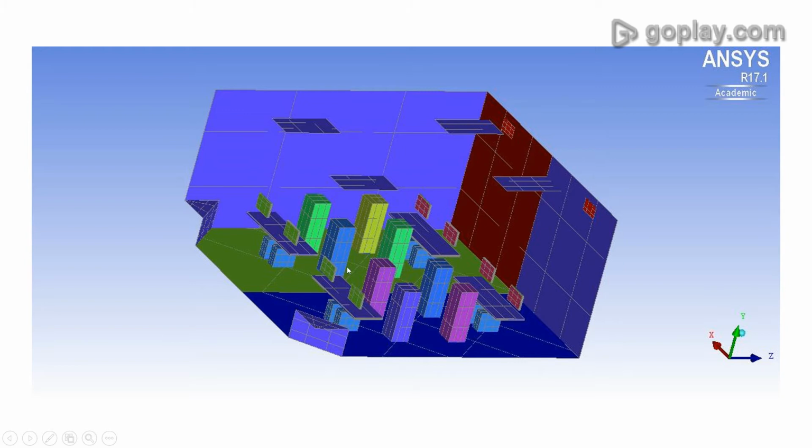Now, secondly, what we will learn in this tutorial is that these inner blocks, the inner furniture, the computers, the monitors and these tall boxes, are an obstacle to the fluid flow. So we will learn that to model such internal walls, we will have to associate the internal edges to the curves inside the geometry. We will associate the internal edges to the curves which make up these boxes. So that will help us create an internal wall.